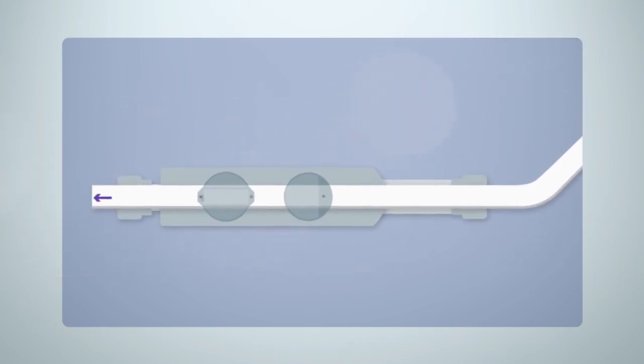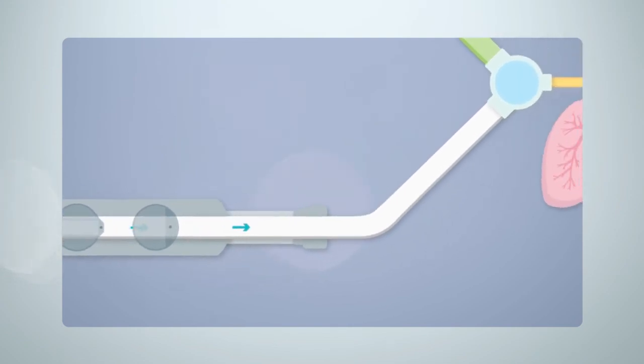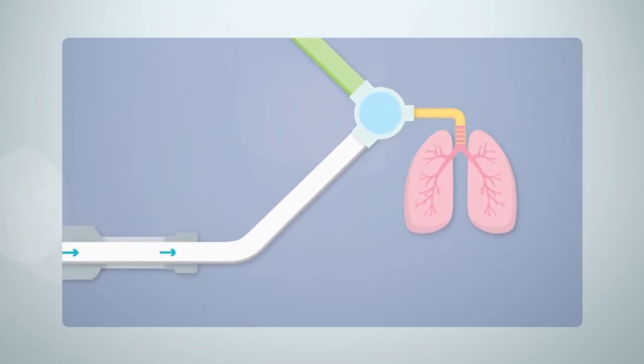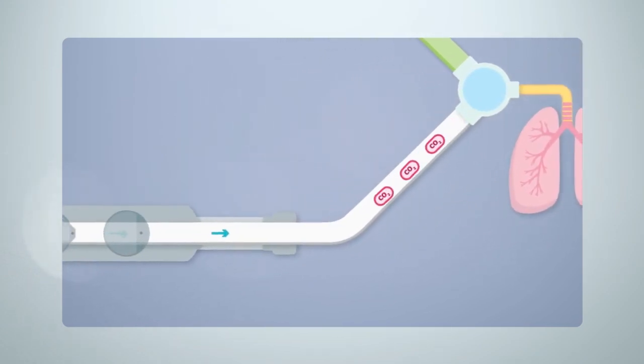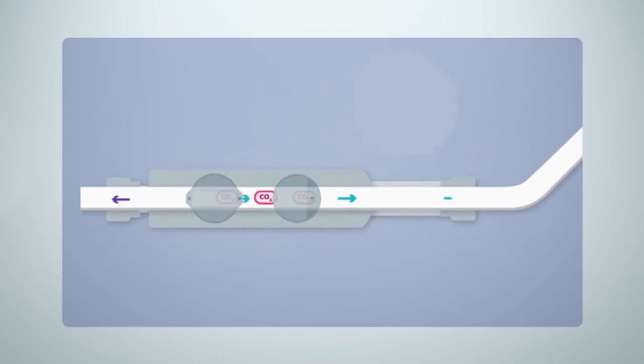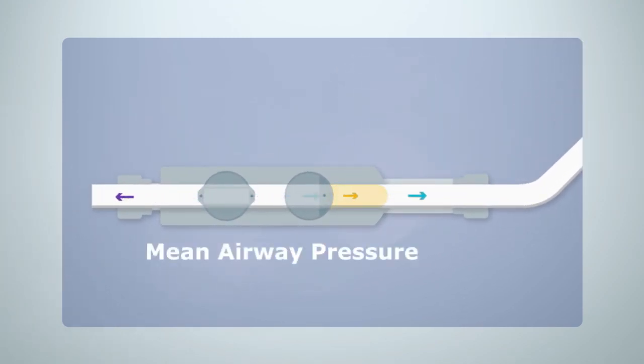It works using a third rear-facing jet which alternates with the forward-facing jet to create a negative flow thereby facilitating active expiration and aiding in the clearance of carbon dioxide. The second forward-facing jet is now used to control the mean airway pressure.